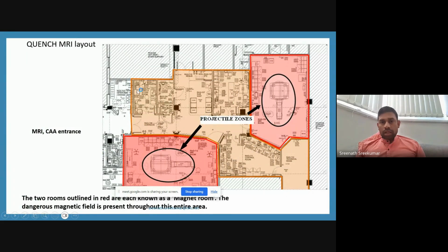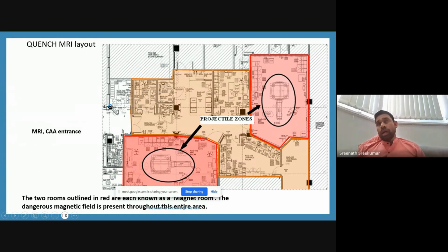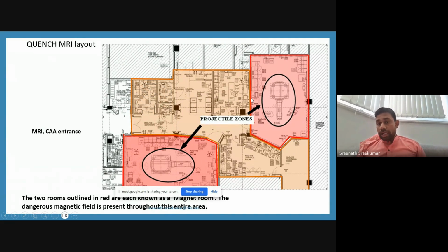Then this is another layout, which is also like two rooms. If we are in the sandwich between a room having two MRI scanners, this should be the system. The projectile zones are marked here, and the red sign denotes the 5 gauss line. So if somebody goes inside without any screening or supervision by other staff, and they have non-conditional devices, they will be in range. That's why we also need to check.